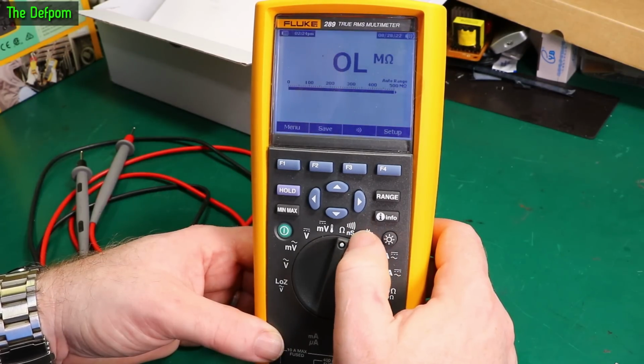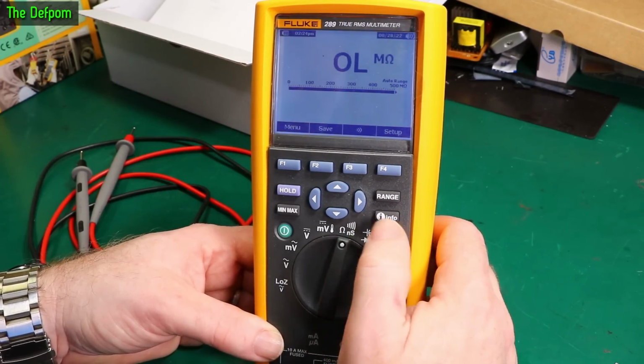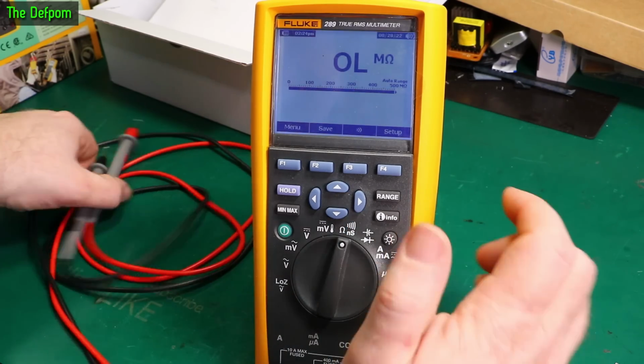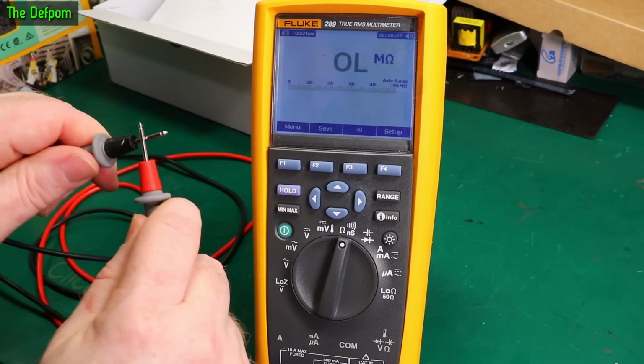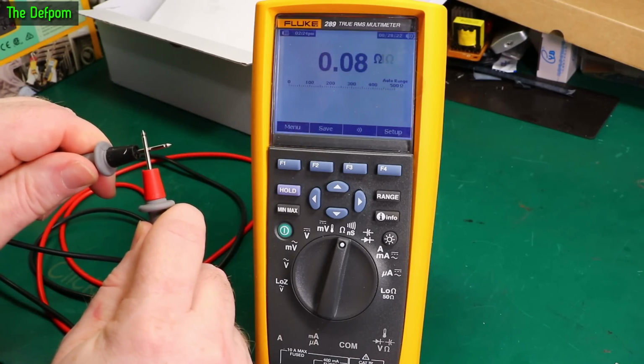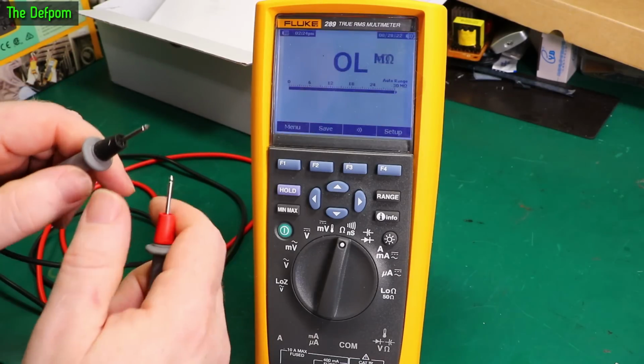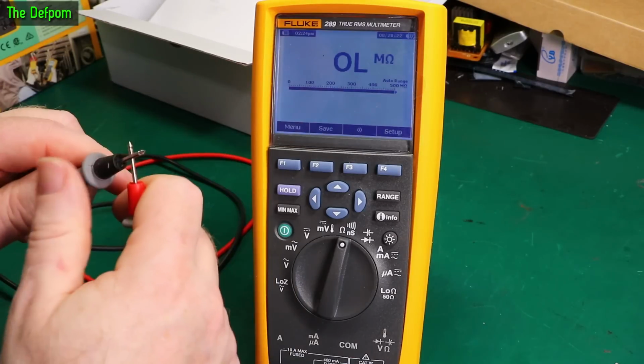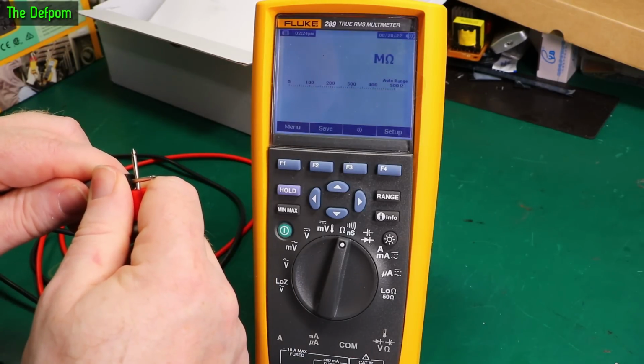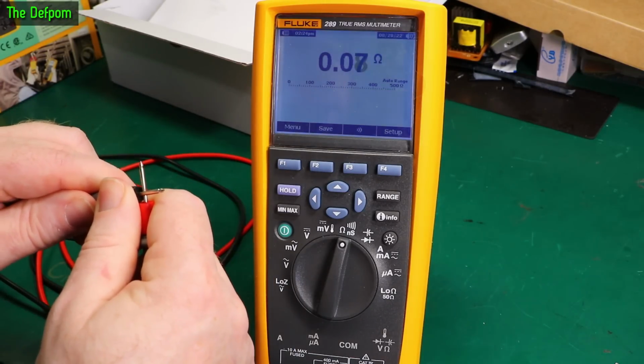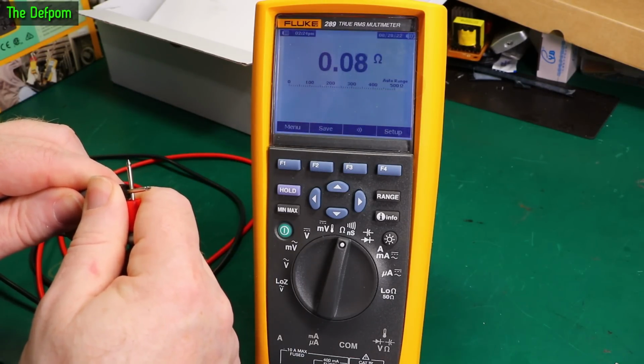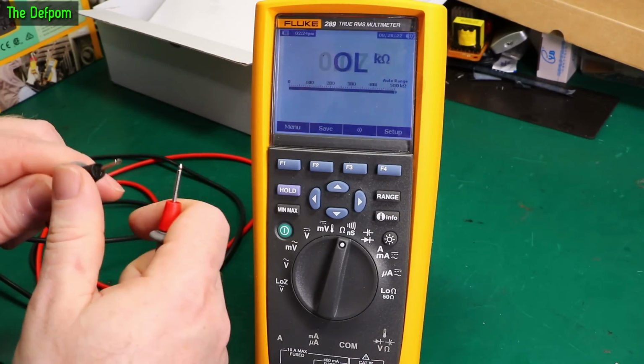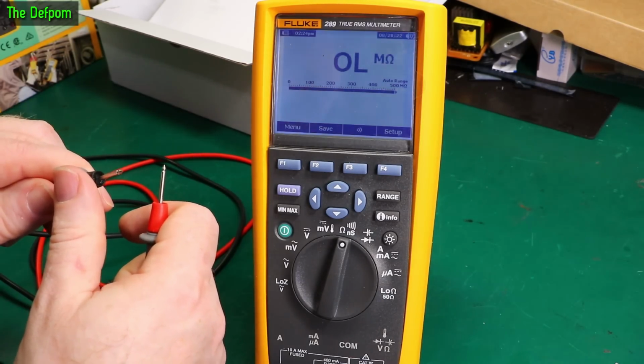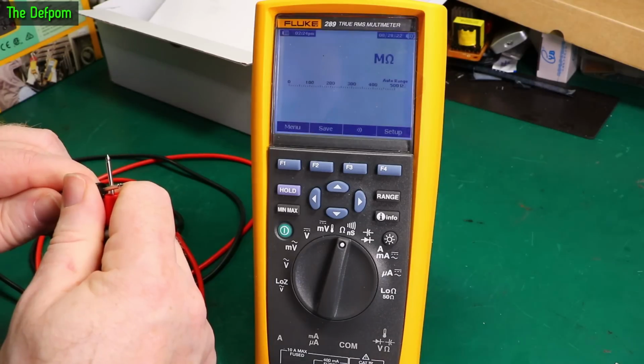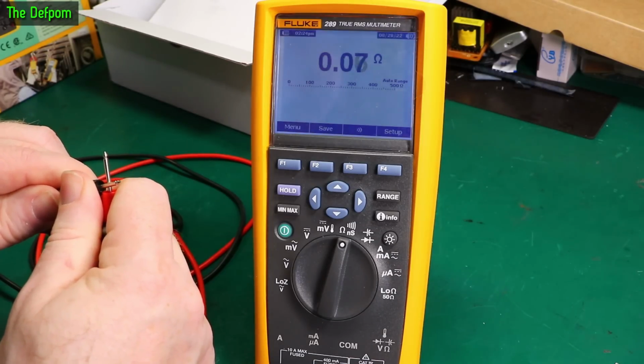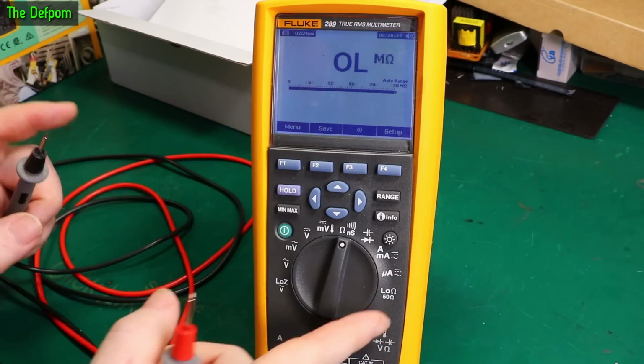Resistance mode - we've got standard resistance, nano Siemens and a sounder. Let's have a look, see how quickly this responds. You see it ranging through - that's a 500 ohm range. It's a 50,000 count meter, by the way, I should point that out. So 500 mega ohms is the top range and 500 ohms the low range. Kind of - there's also a second range over here, we'll get to that.